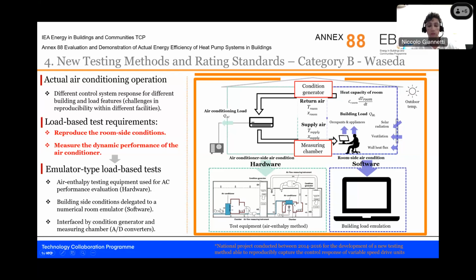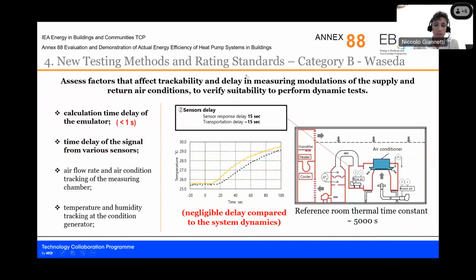This is done with a method that we called emulator type load-based test that uses the same testing equipment as the current standard, so a simple air enthalpy testing facility, and combines this with software that we call the room emulator, to which we delegate numerically the task to calculate in real time the evolution of the indoor space condition according to the cooling or heating effects applied in real time and measured in real time by the unit that is tested in the testing facility. So the communication between hardware and software is possible through two main devices, the condition generator or reconditioning unit of each psychrometric room, and the measuring chamber where we can obtain real-time measurement of cooling and heating effect.